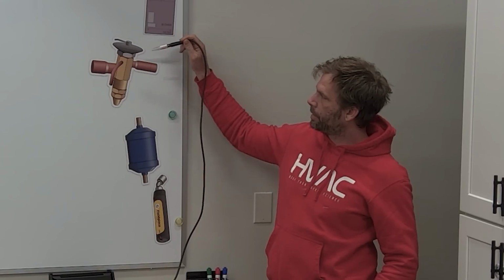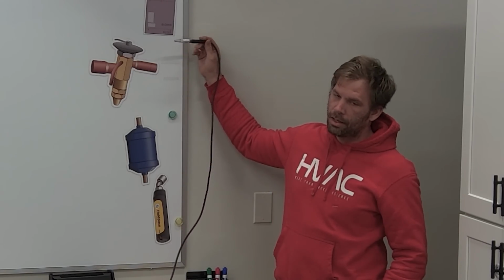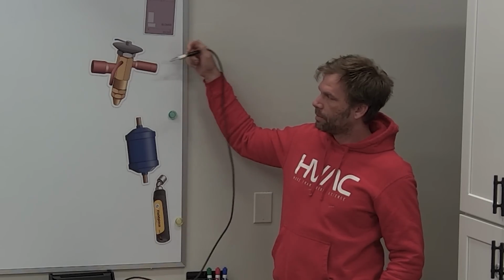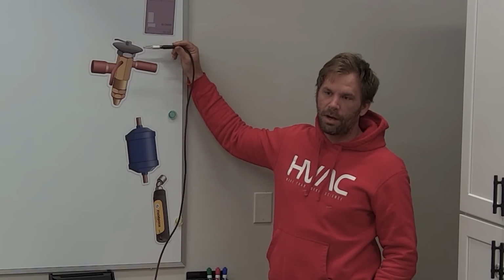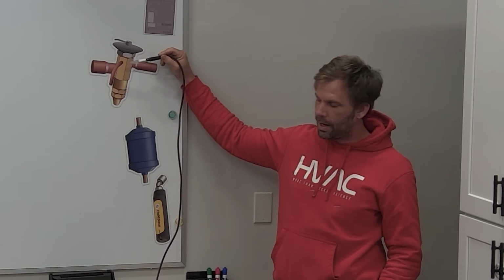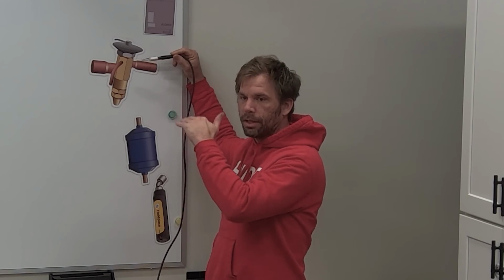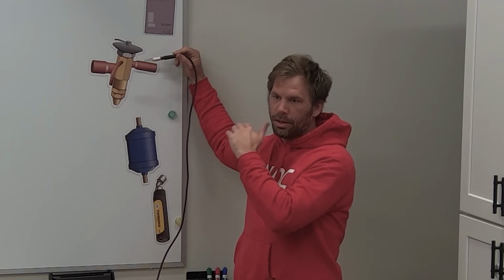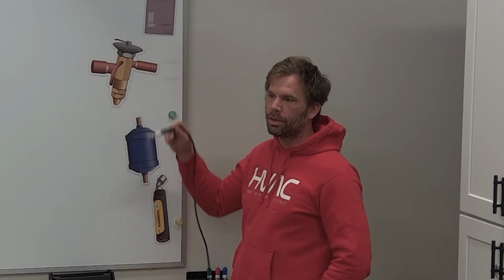I move a little bit closer, and it's going to be a higher amount of refrigerant hitting the sensor because I'm moving closer to the leak. Now it's going to go off again. But you sit there for a while, and in auto, it's going to adjust one more time to a new baseline. And it lets you get closer and closer to large leaks or when you have multiple leaks on the system. How might that get in the way if you're trying to find a leak? How could that potentially make it harder for you guys?